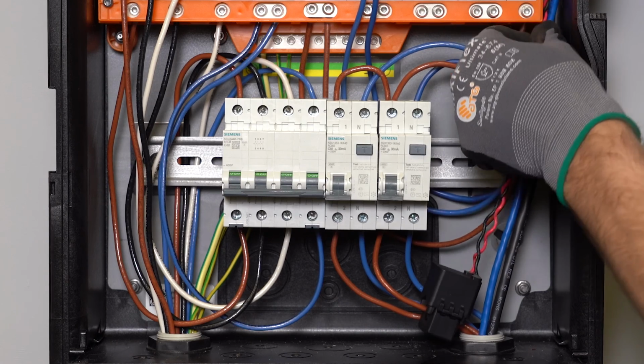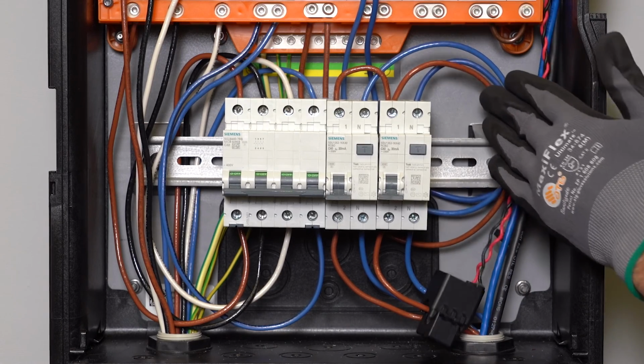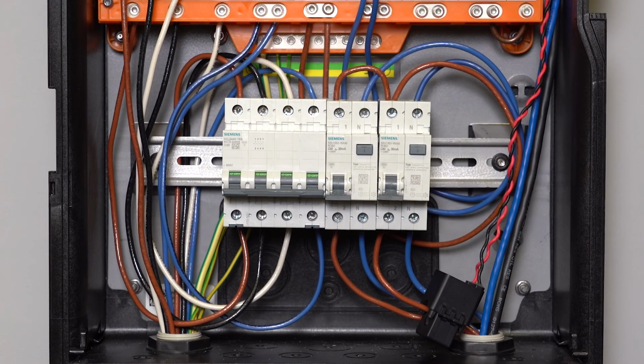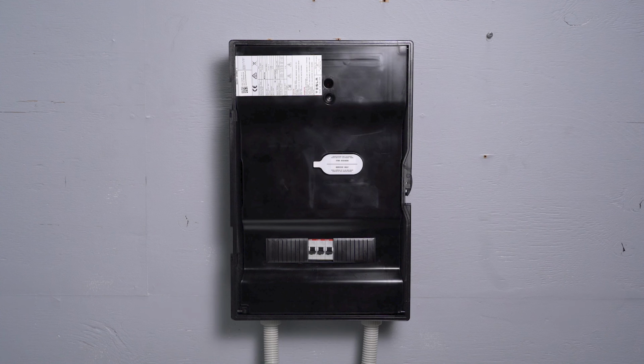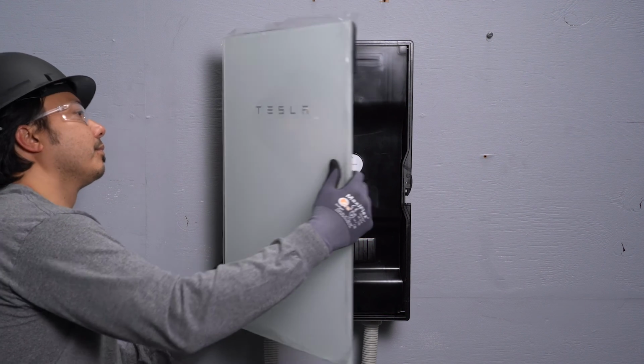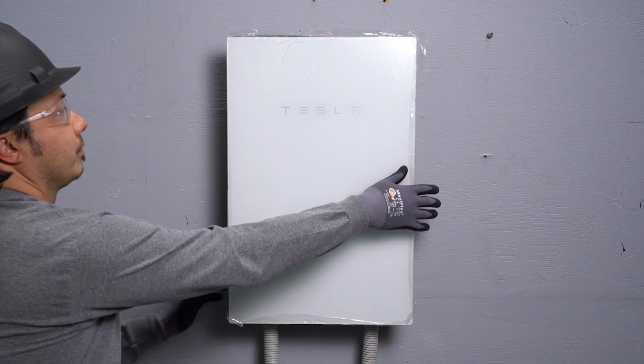Once all connections are made and energy meters installed, test the circuits and neatly manage all wiring inside of Backup Gateway. Take photos of all work done and replace the dead front panel and install provided snap and breaker fillers in any empty slots. Finally, mount the glass enclosure door. The system is now ready for commissioning.